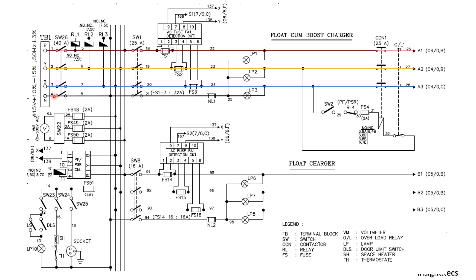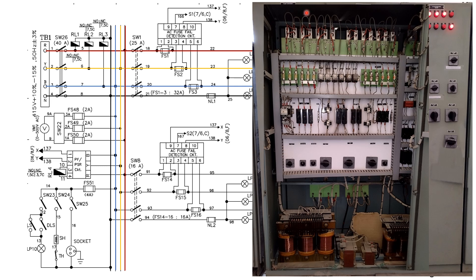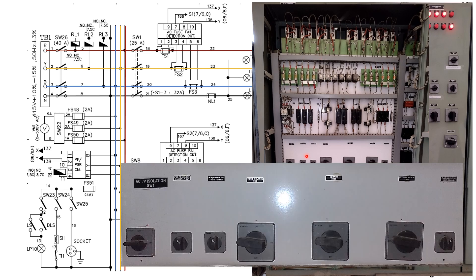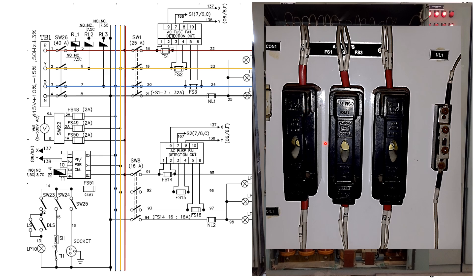We have three-phase AC supply. From switch SW26, the supply will move forward into the AC bus. After that, through switch one, we can turn on the boost charger. From switch one, we are having the provision for fuse FS1-3 and neutral link. As we have seen, behind the door of the boost charger you will get the complete circuit. This is switch one — if this is on, you can turn on the boost charger. After that, we have fuse FS1-3 and neutral link.